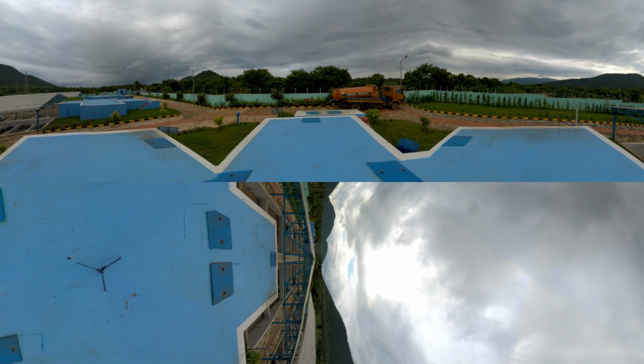Stabilization reactor. After the large solid particles are removed, the liquid sludge flows from the screen chamber to the stabilization reactor for further treatment. The stabilization reactor has 3 chambers. The raw fecal sludge is introduced into the first chamber where it undergoes stabilization for 2 days, during which the degradable solids settle at the bottom and the liquid flows into the second chamber. This liquid stays in the second chamber for 10 days, during which the remaining solid settles.